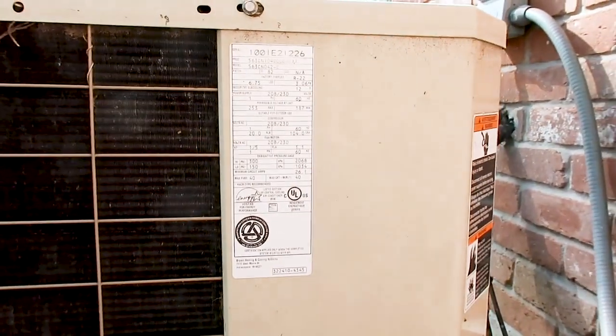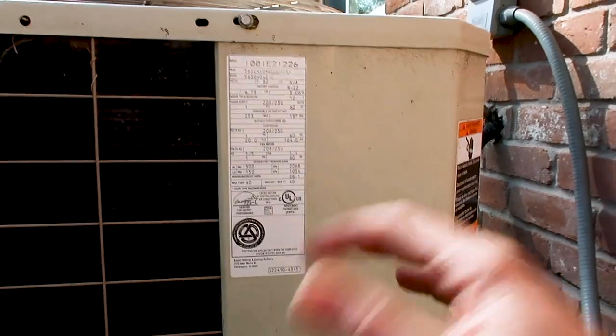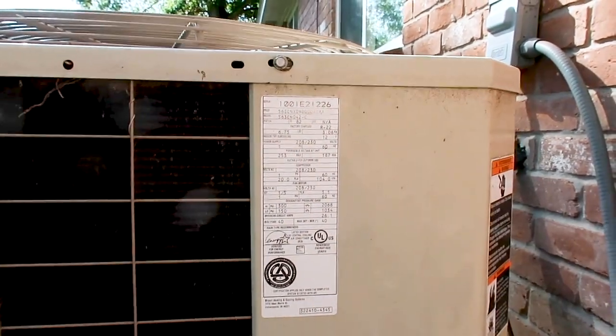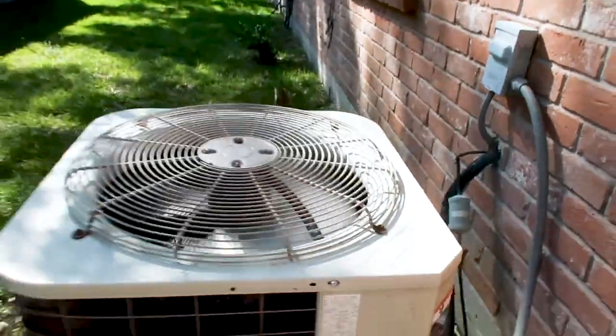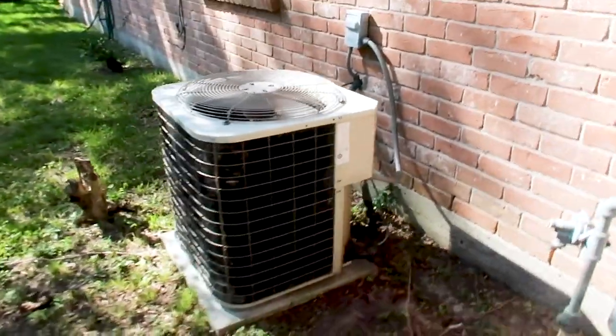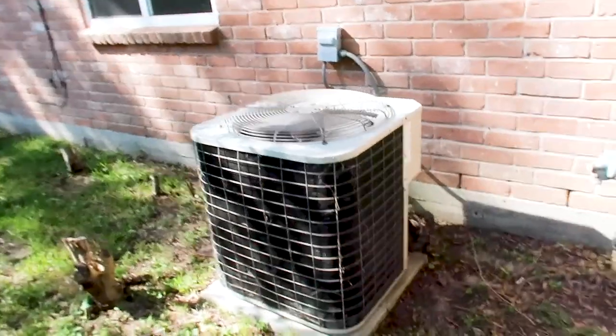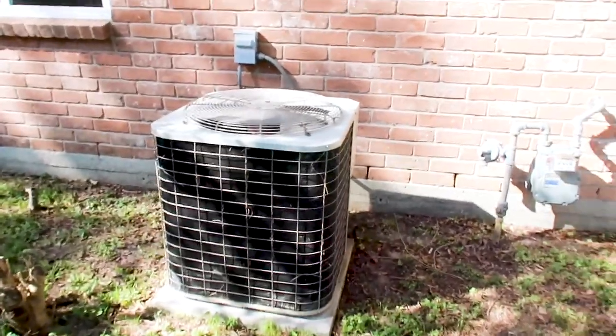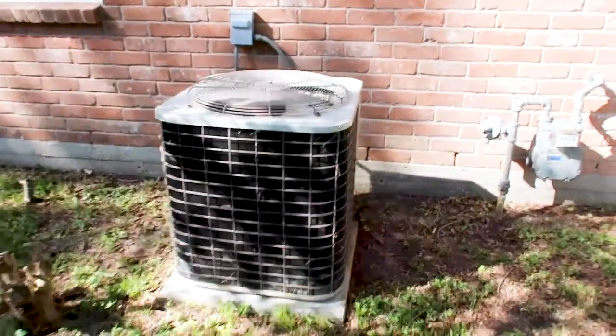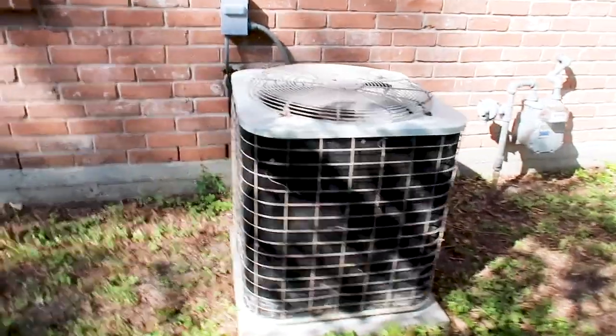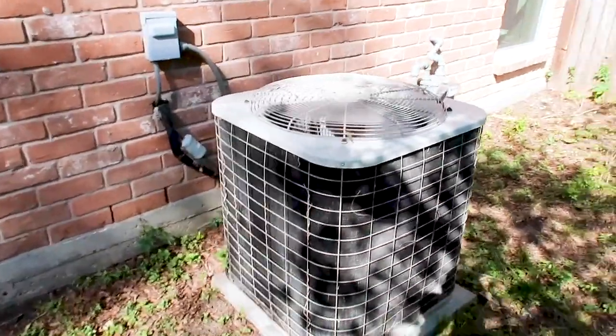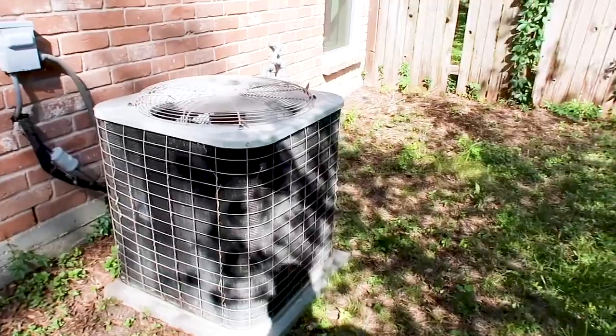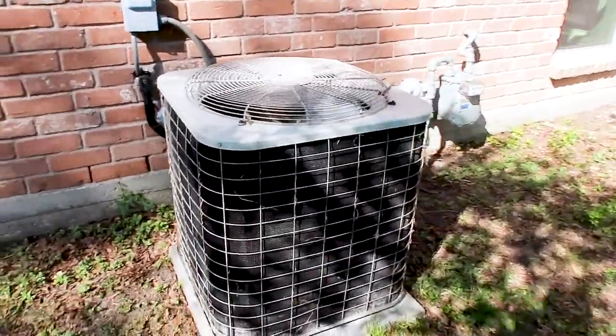You want to pull off your breaker size to make sure your breaker matches inside. We're going to educate the client, let them know the size and the year. It's R22 Freon, so this is a discontinued unit, and it's 19 years old. So we'll let them know it's approaching the end of its life expectancy, and that this unit probably doesn't have much life left on it.